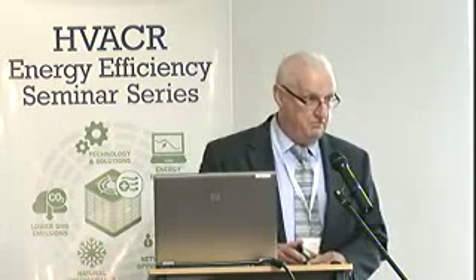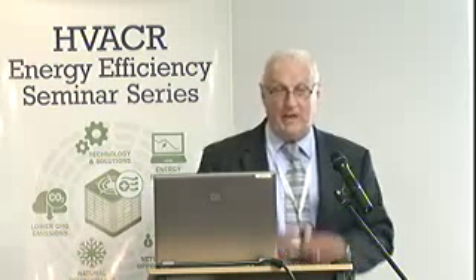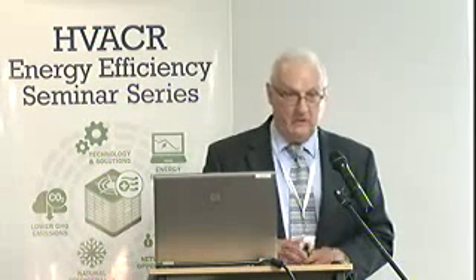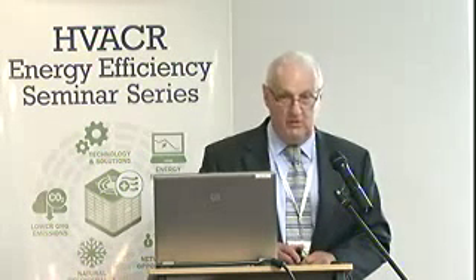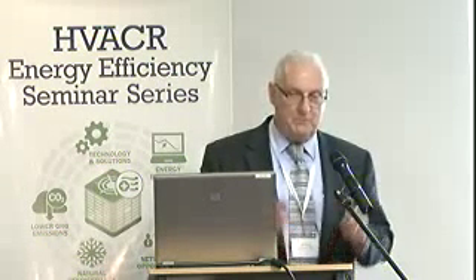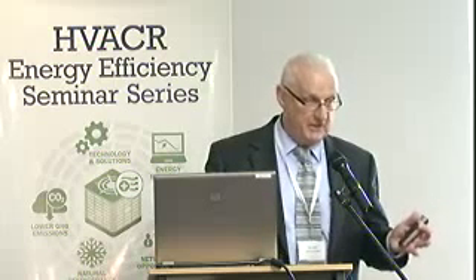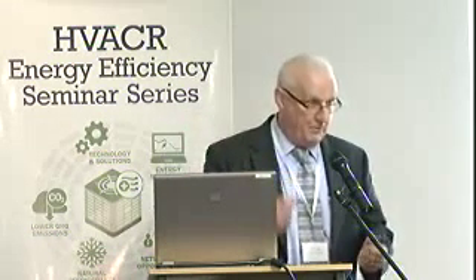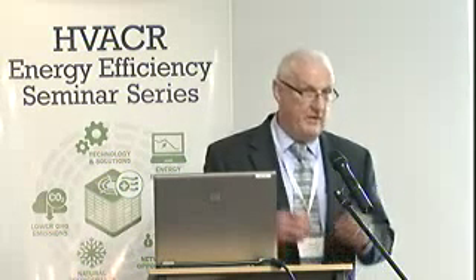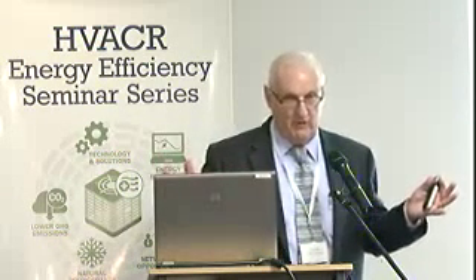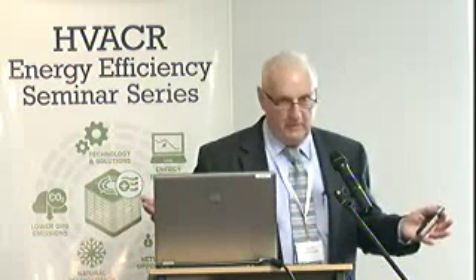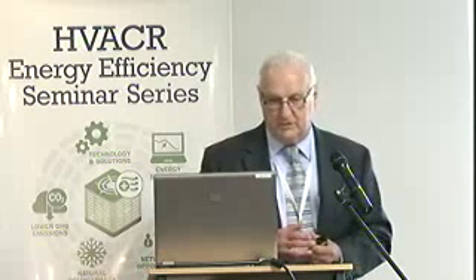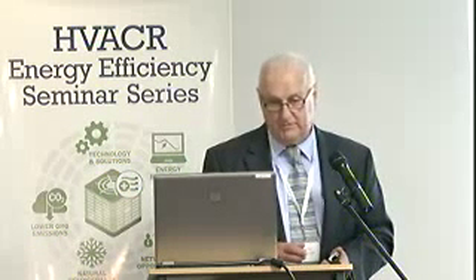I should also mention, it's a very fast unit with 16 milliseconds. It's 0.016 seconds response time, where it actually adjusts the voltage. We have independent phase and automatic phase control, so that each phase is adjusting independently. We have surge protection, and importantly, and particularly for refrigeration loads, I just insist that they go in, we have a bypass switch, so a physical bypass can take place of the unit for either maintenance or repair if that was ever required, or for whatever reason that the customer decided that they needed it out of circuit, rather than have to go through another power interruption.